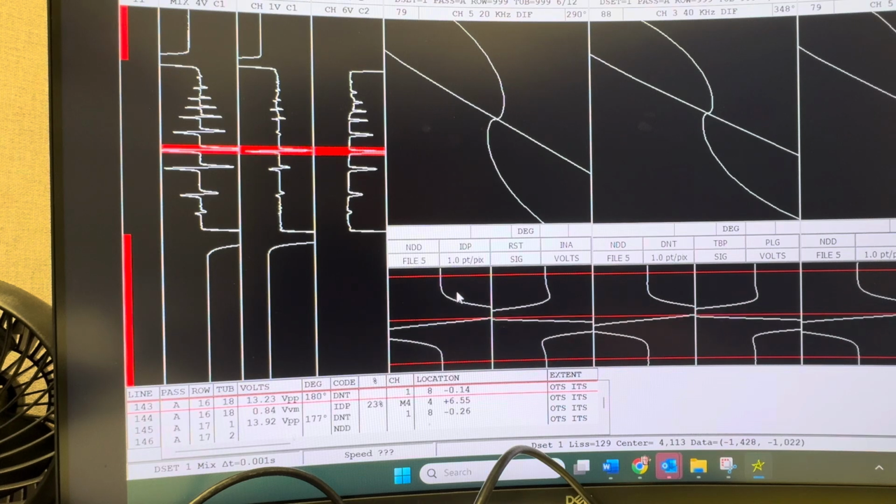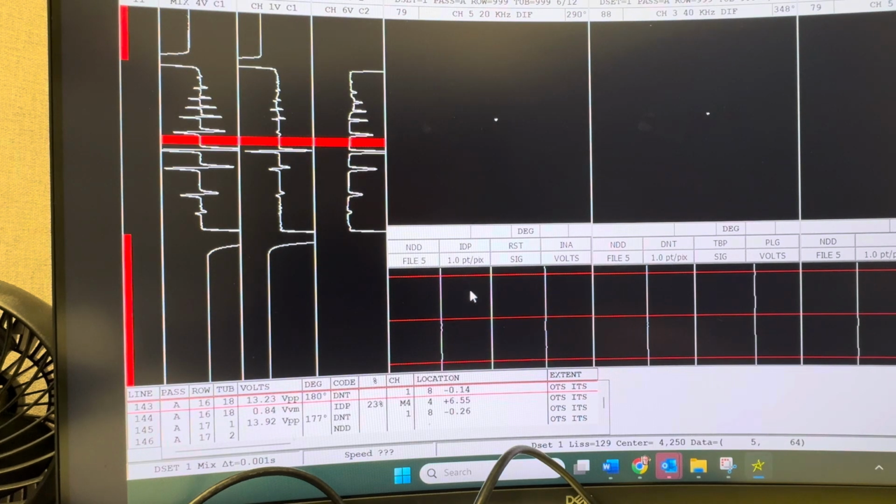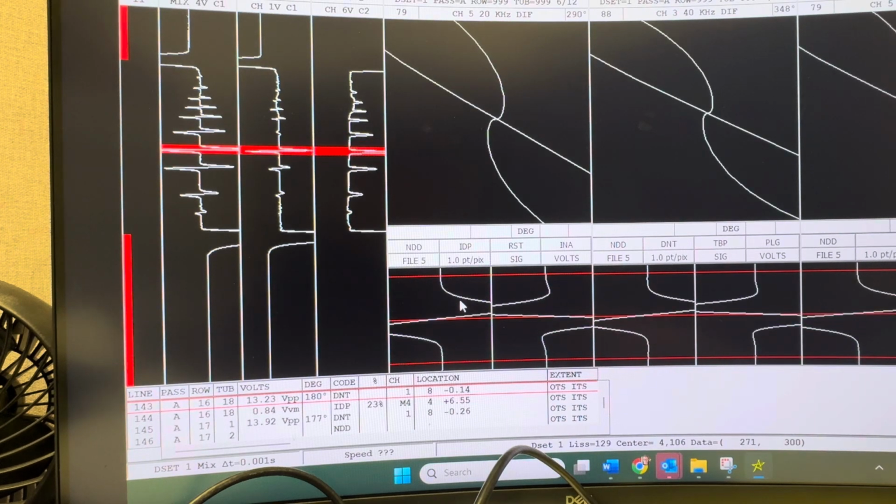So let's just say that this was your differential coil in a cross-axis probe. When you click over to the cross-axis coil channel, that data would be up here somewhere. It wouldn't be in your expanded strip charts. To see what sort of response you're getting from the cross-axis, you'd have to go and scroll down in the cross-axis channel and be around in here somewhere. But data slewing lets you align data from different coils to appear at the same time in your display.